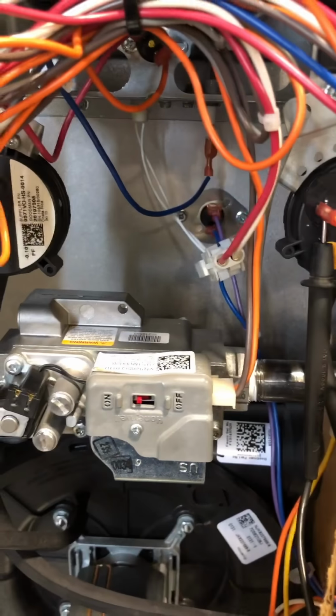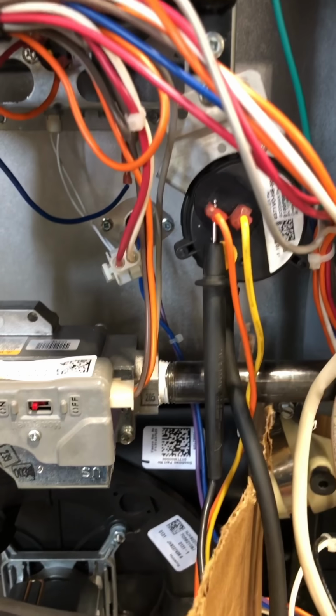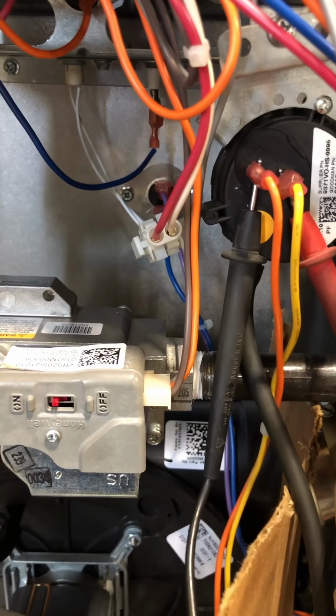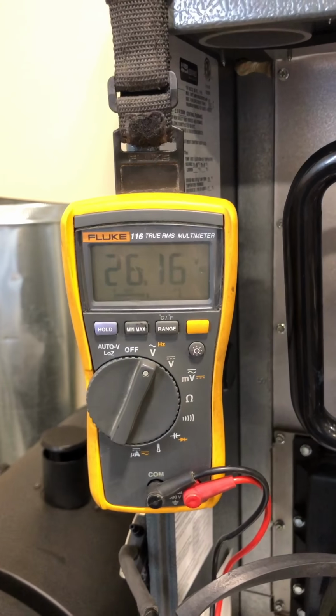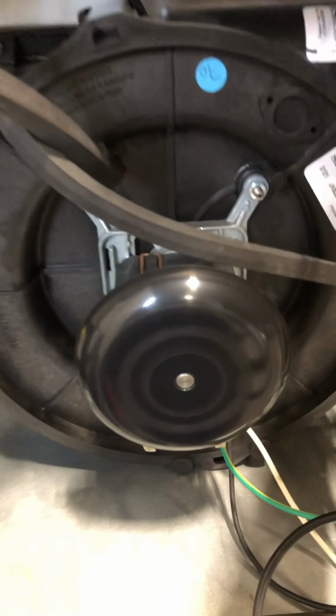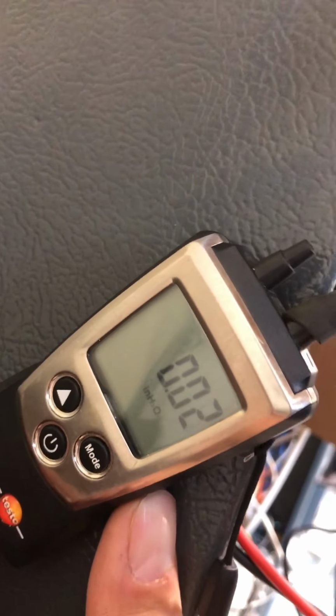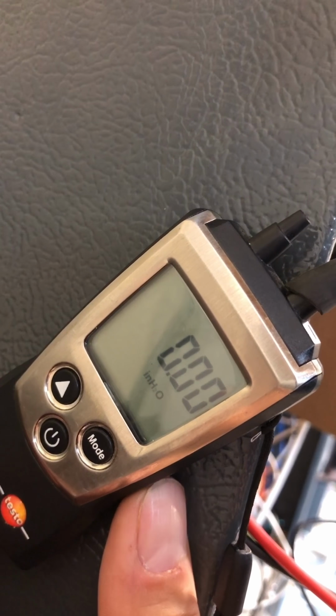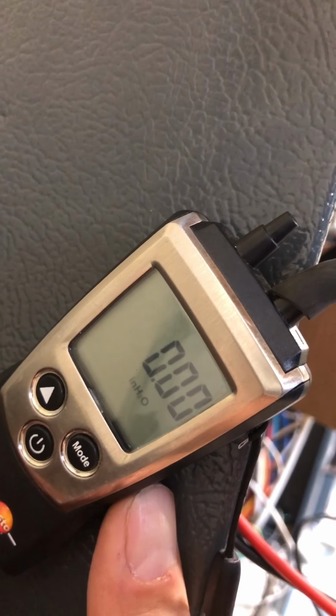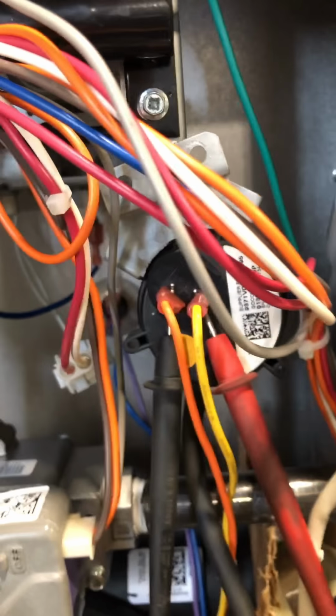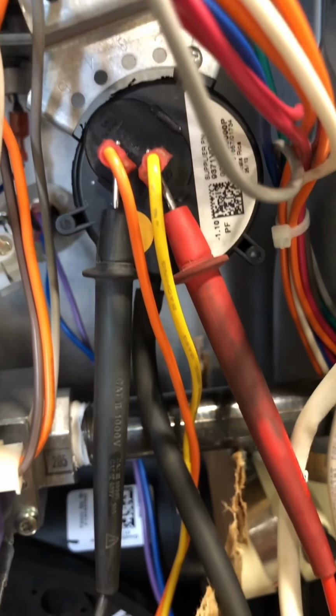Okay. And of course my probe fell out. We have an open switch. Yes, the inducer motor is running, but we are not pulling the proper vacuum. We're not pulling any vacuum at all, really. We needed 1.1 inches of water column, negative pressure, in order for that switch to close. So that switch is operating properly, and nothing wrong with that switch. We're not pulling the proper vacuum.